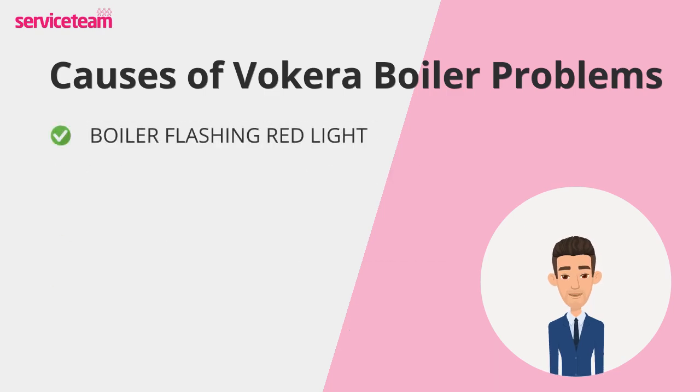A flashing red light is bad news. It usually means ignition failure. Resetting the boiler might help, but if the problem continues, it could point to faulty ignition components or even the gas supply. This is a critical issue that needs urgent attention from a gas-safe professional.